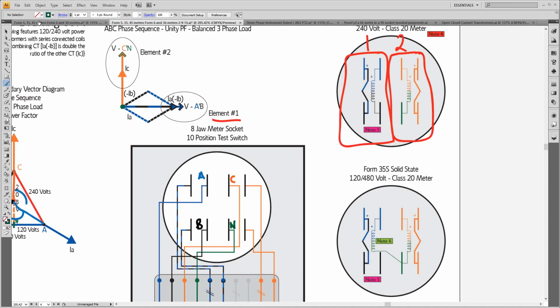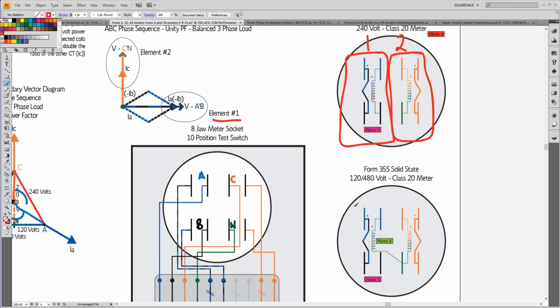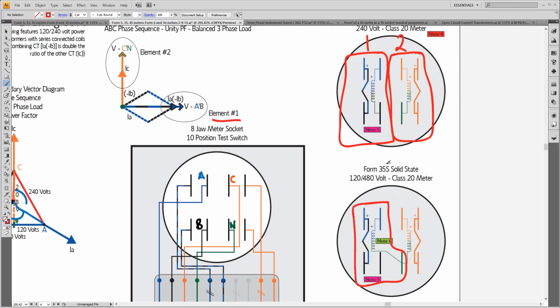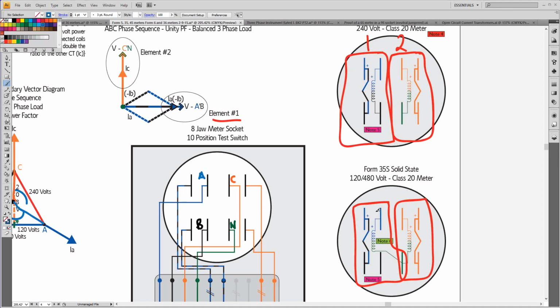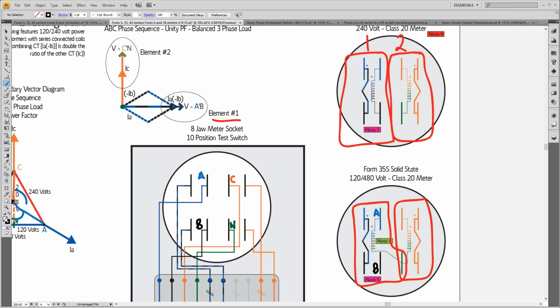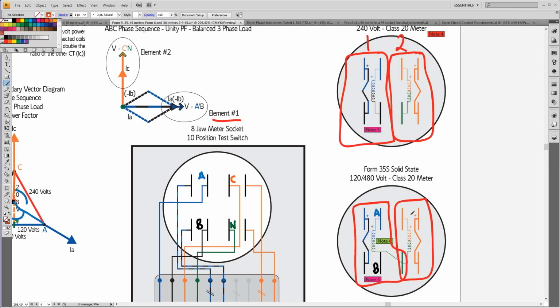some rectangles here again. This is a meter element. That includes that right there. And then this would be a meter element that shares that same point. Over here, two separate potential coils. I drew two pretty symmetrical rectangles. Here, this potential coil is connected to neutral. This potential coil is also connected to neutral. And so as you look at this on how it's connected from the socket, as I plug that into the socket, I have A phase here. I have B phase voltage, B phase sitting here. Nothing connected to that in the meter. See here, and neutral here.